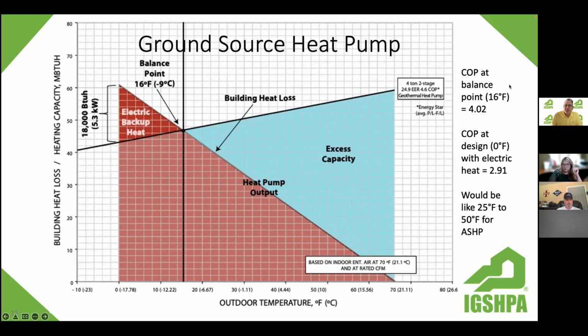In all fairness, since we looked at the COP for air source heat pumps, we should look at the COP for geothermal heat pumps with electric heat, because we show some electric heat here. At the balance point, we have a COP of 4.02. So for every unit of energy we're using, we're getting 4 units of heat out of that particular application. If we look at design conditions, this does include electric heat. So our combined COP when it's 0 degrees outside for this application is 2.91. So almost 3 COP with electric heat on the coldest day of the year.